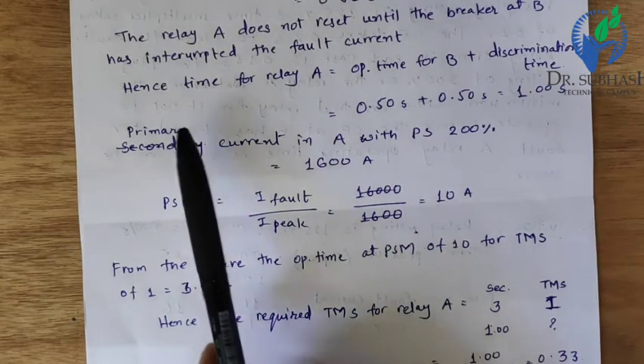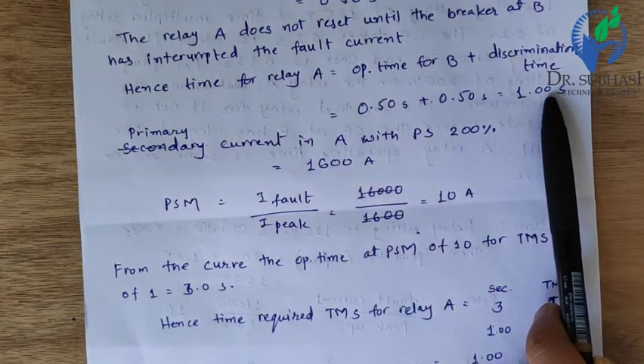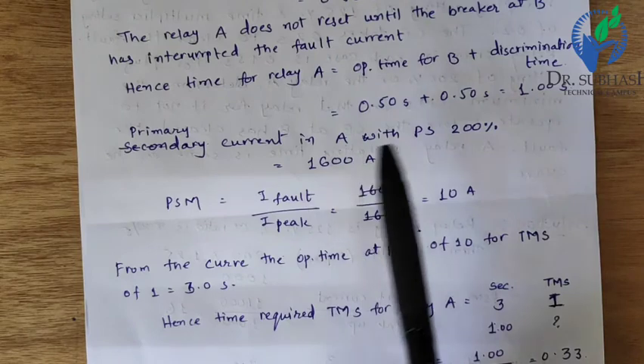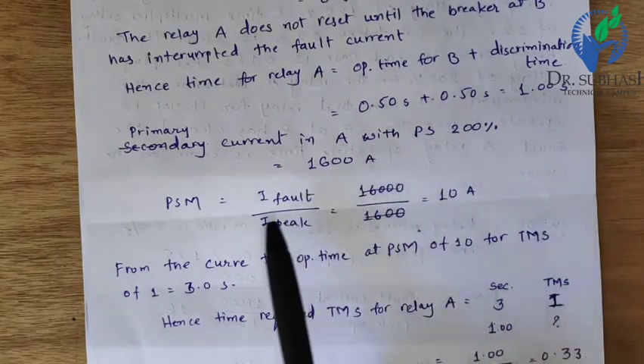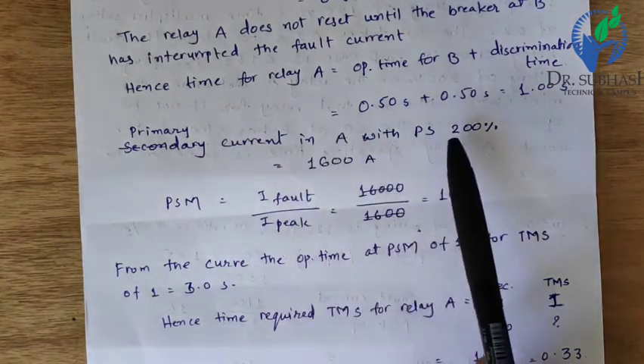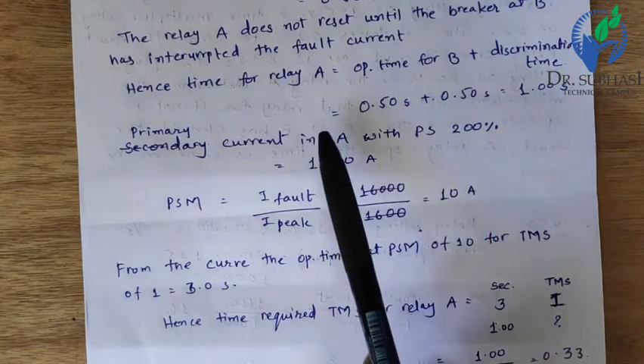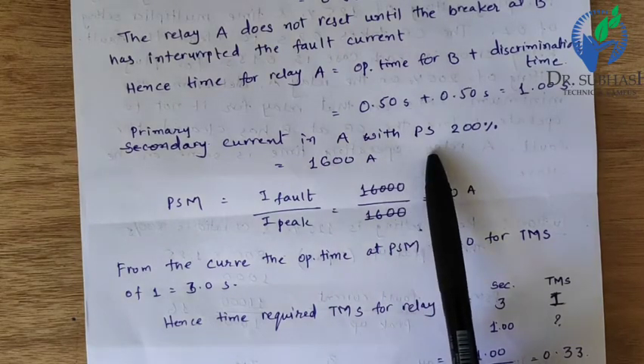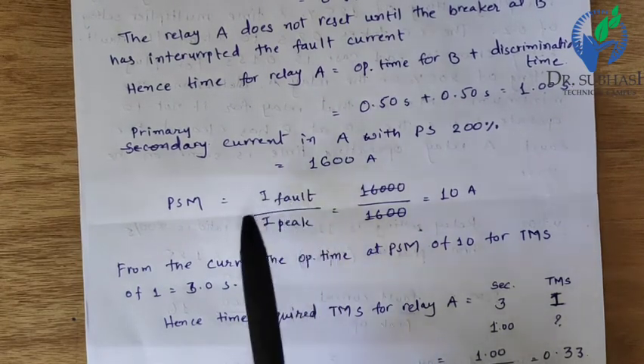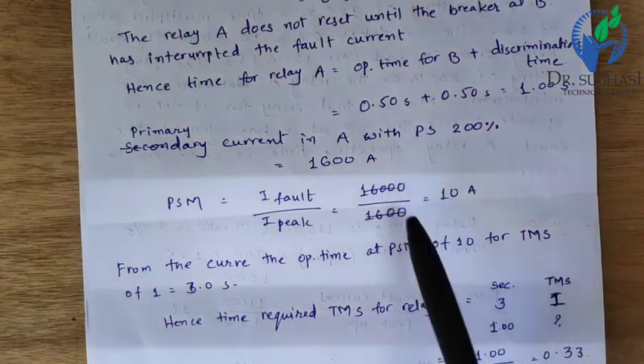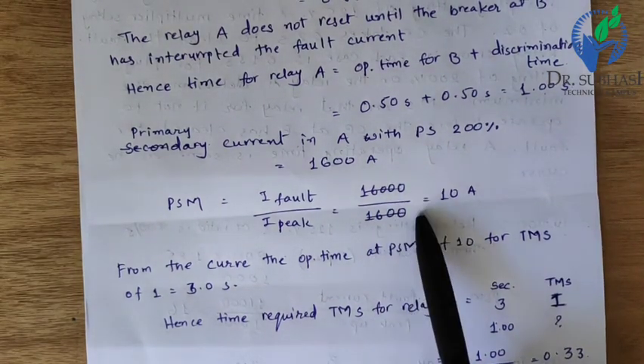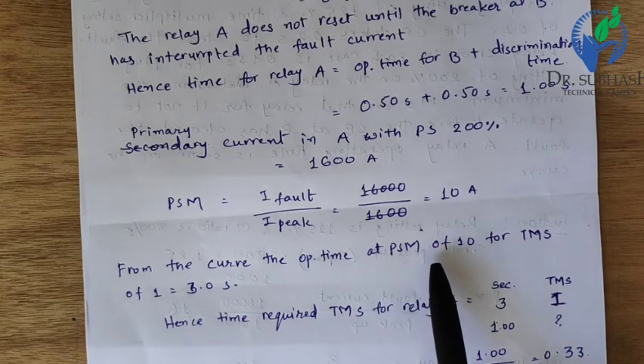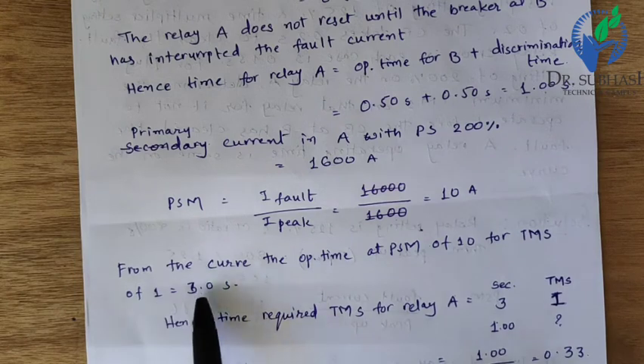The required time for relay A is 1 second. For finding the PSM of relay A with 200% plug setting, the pickup current is 1600 A. PSM = 16,000 / 1,600 = 10. From the curve, at PSM of 10 and TMS of 1, the operating time is 3.0 seconds.